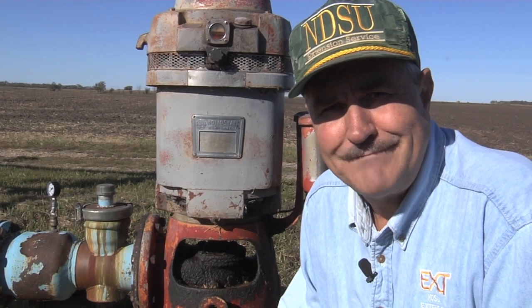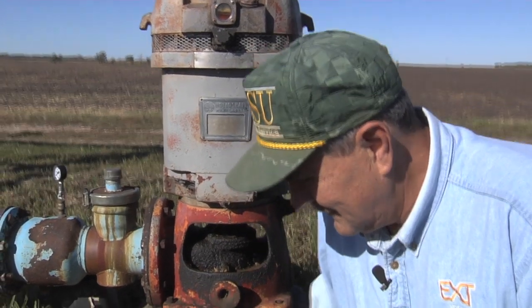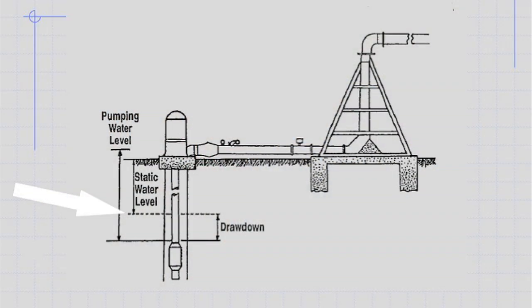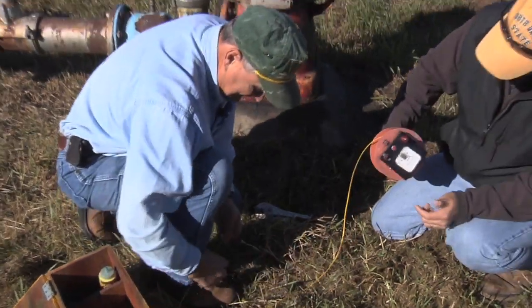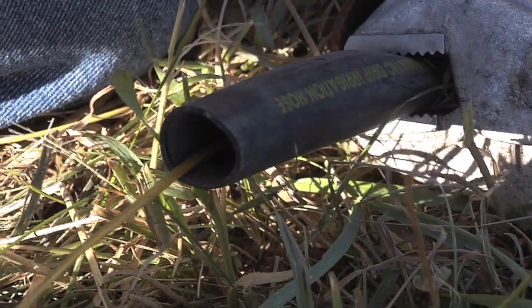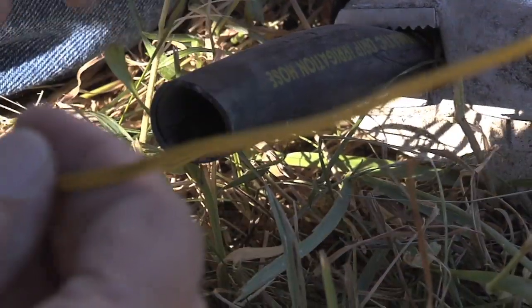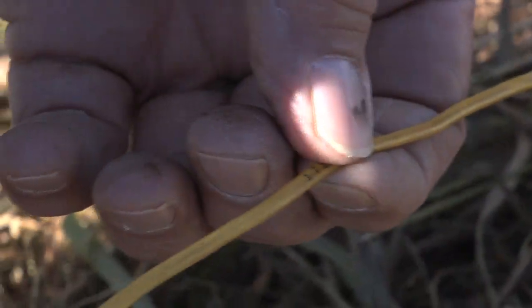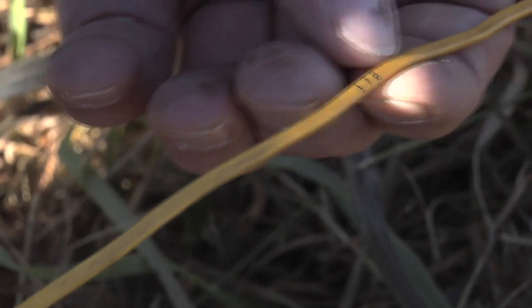So before it ever starts, I'm going to try to determine where the static water table is, just so I have a reference point. So when we measure the water level while this pump is actually pumping, I have some idea of what the drawdown is in the well. This thing has markings on it of how many feet it's going down. This is an old system, and over the years we've lost a few feet. Luckily I haven't, but some of my predecessors got these caught in the pumps and lost them.